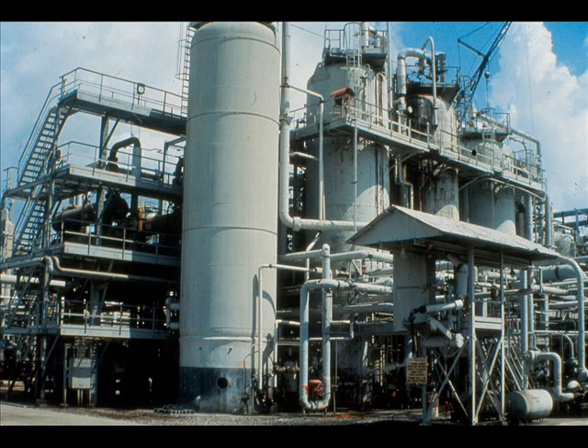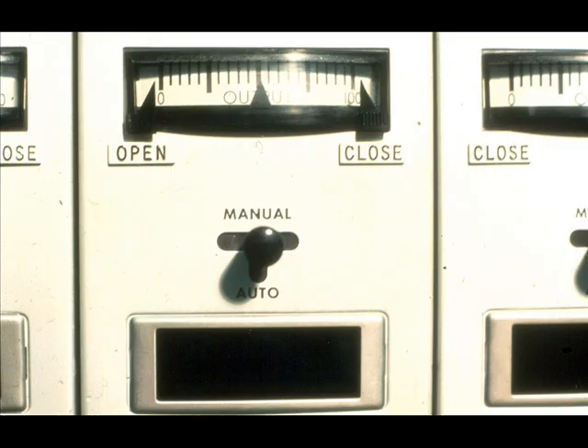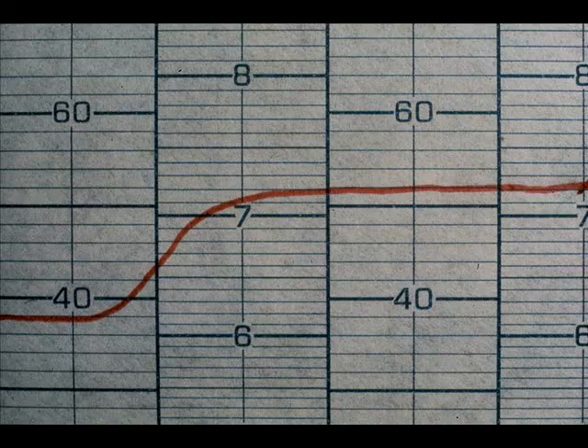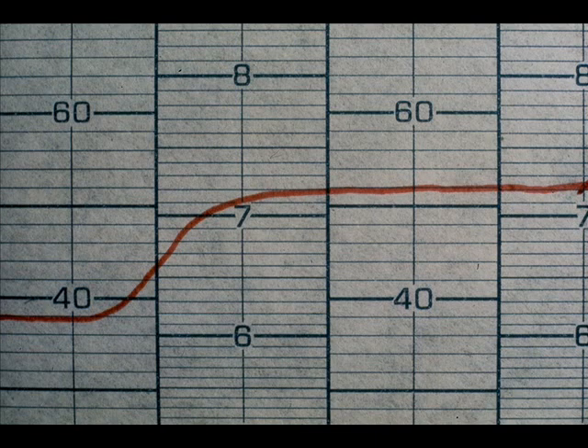The Ziegler-Nichols Reaction Curve Method will use information revealed by the process reaction curve. The reaction curve is the process response to an open-loop step change. The controller is placed on manual, and a measured percent of output change to the control valve is made. The process reaction is observed by watching the process variable record.